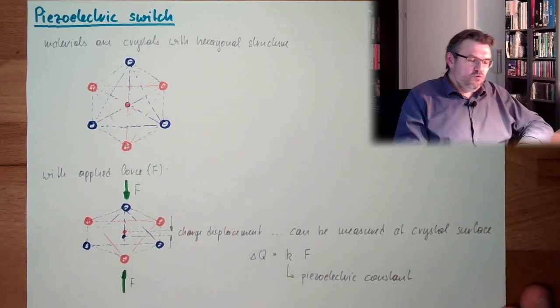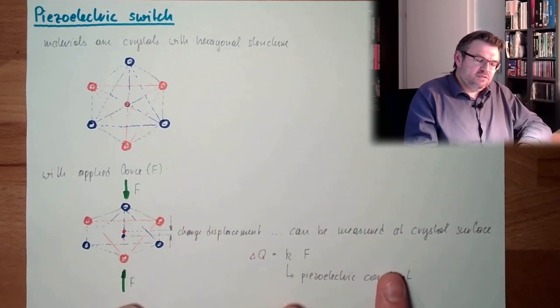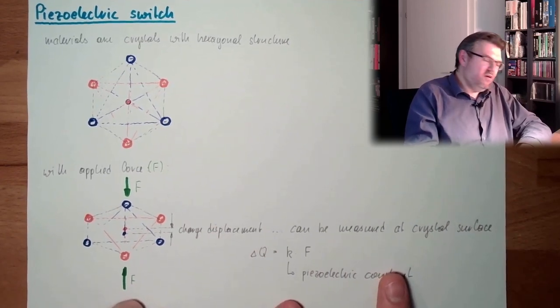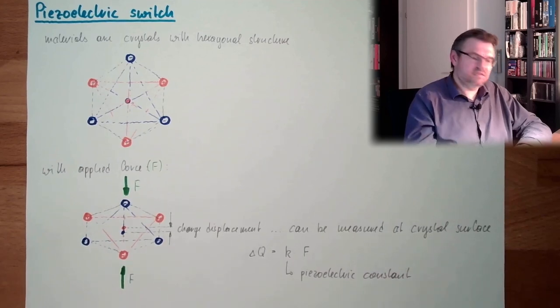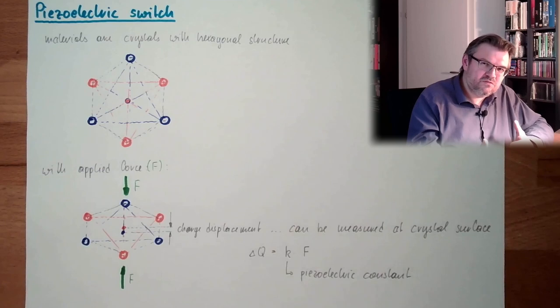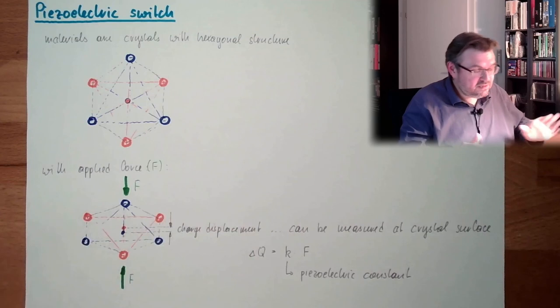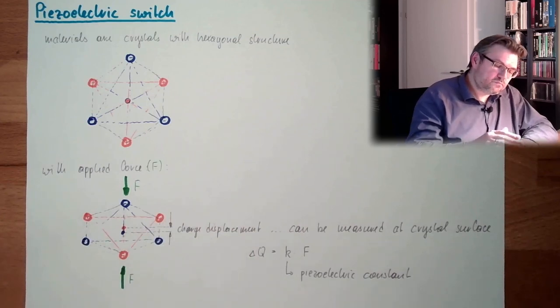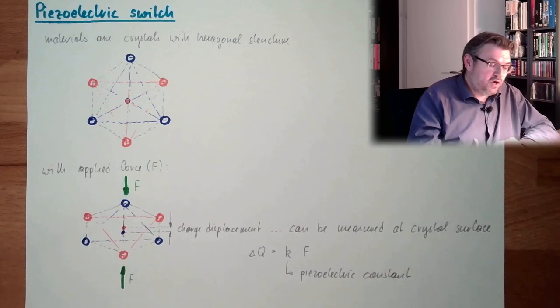And if you are measuring, you need to have a special amplifier for these charges, because this has to have a really high input resistance, because those small charges, they need to stay at the crystal, because otherwise, they cannot be measured. So you need a special type of amplifier, called charge amplifier.